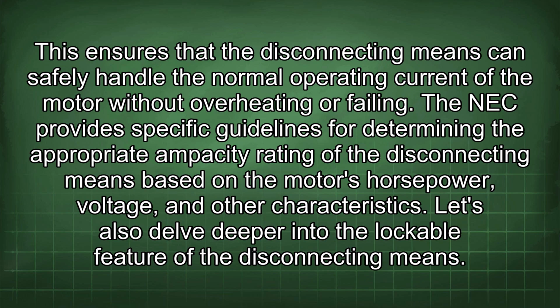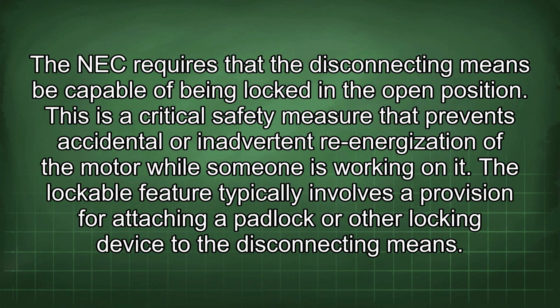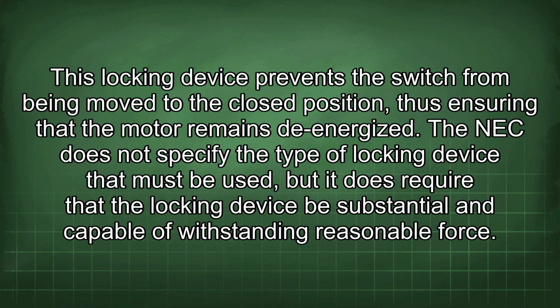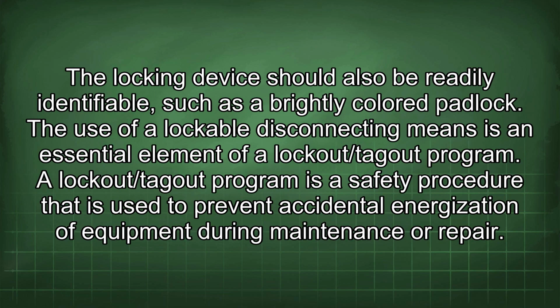Let's also delve deeper into the lockable feature of the disconnecting means. The NEC requires that the disconnecting means be capable of being locked in the open position. This is a critical safety measure that prevents accidental or inadvertent re-energization of the motor while someone is working on it. The lockable feature typically involves a provision for attaching a padlock or other locking device to the disconnecting means. This locking device prevents the switch from being moved to the closed position, thus ensuring that the motor remains de-energized. The NEC does not specify the type of locking device that must be used, but it does require that the locking device be substantial and capable of withstanding reasonable force. The locking device should also be readily identifiable, such as a brightly colored padlock.